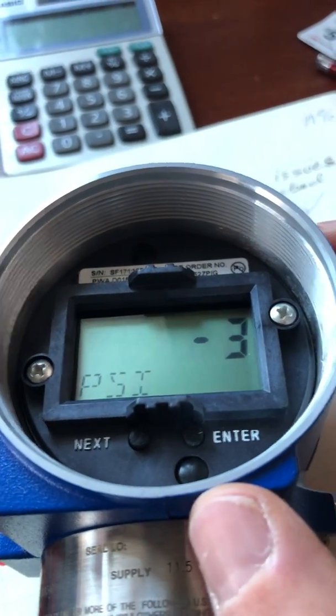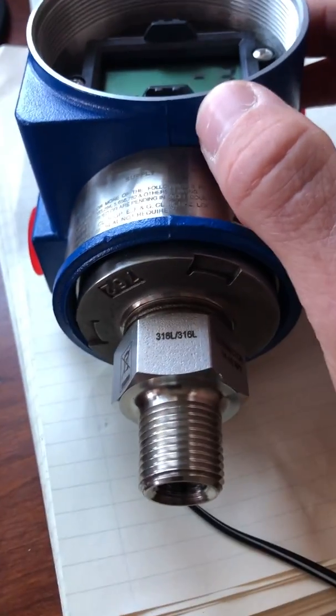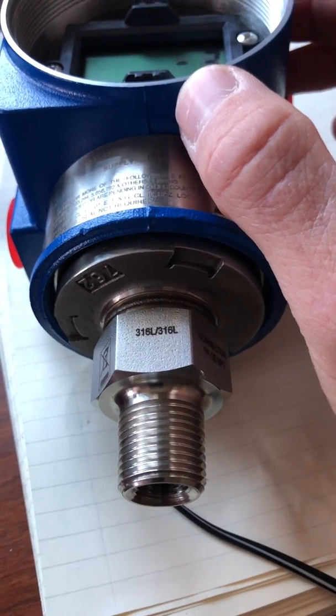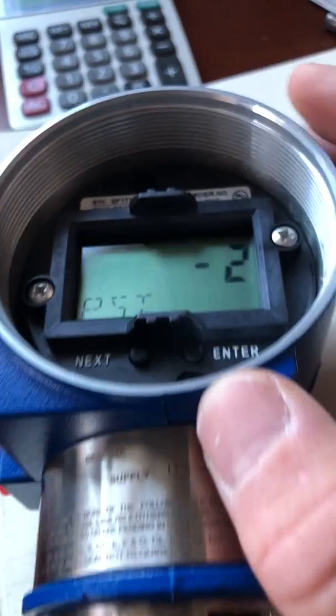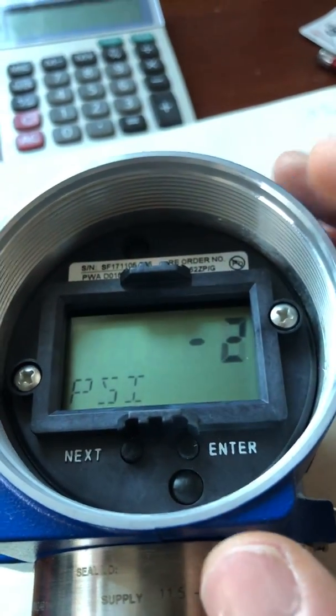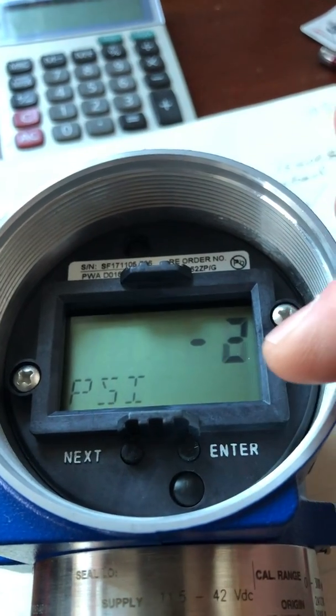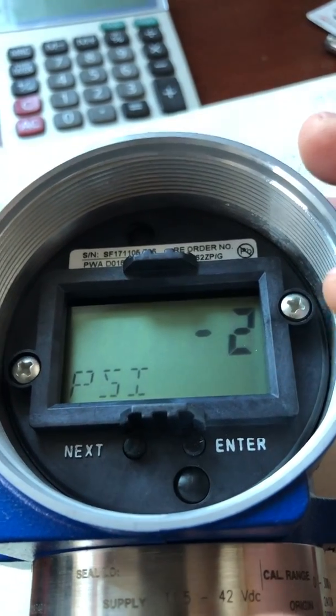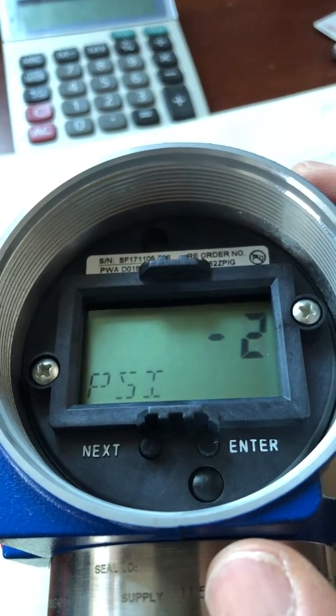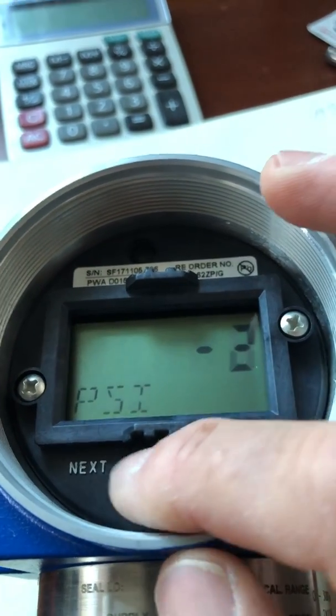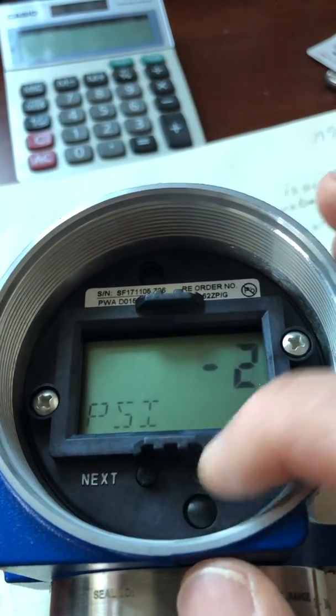So we're starting out with a brand new pressure transmitter. I've got it just sitting here. It's out of the box, it's never been calibrated. You could see that it thinks I'm at negative 2 or 3 PSI because it has not been calibrated at zero yet. So what we're gonna do is there's only next and enter.